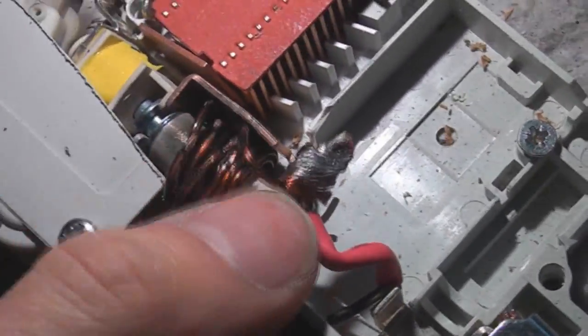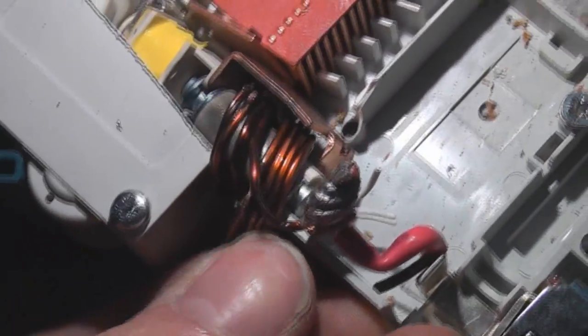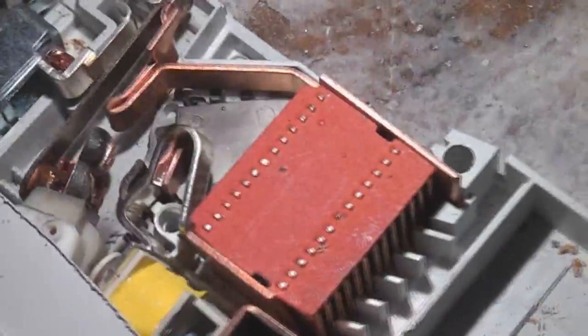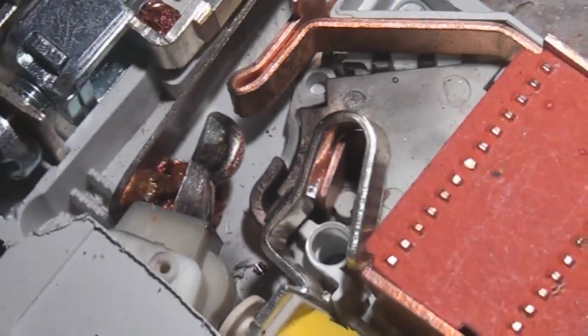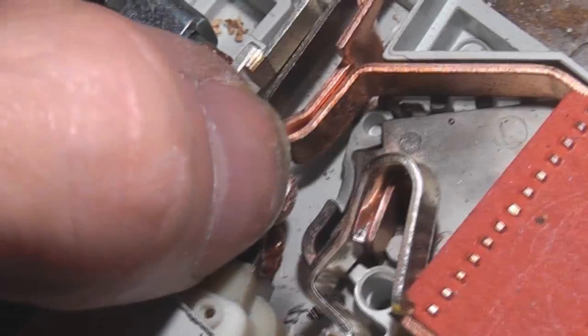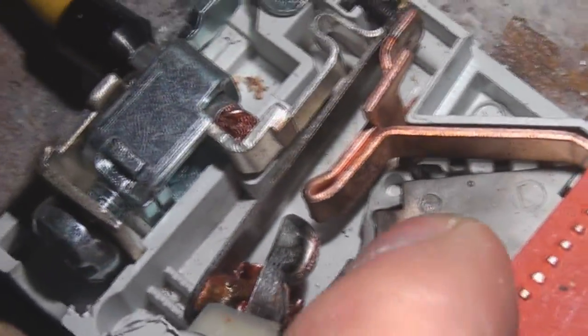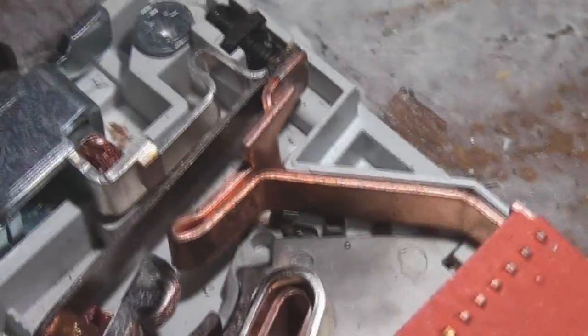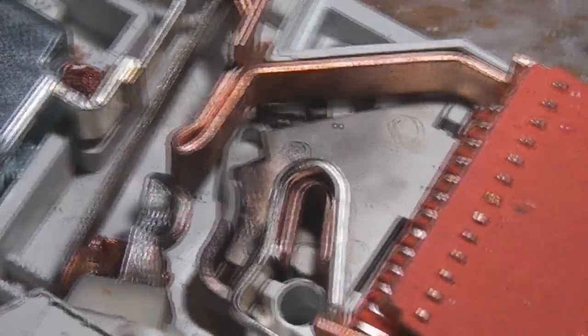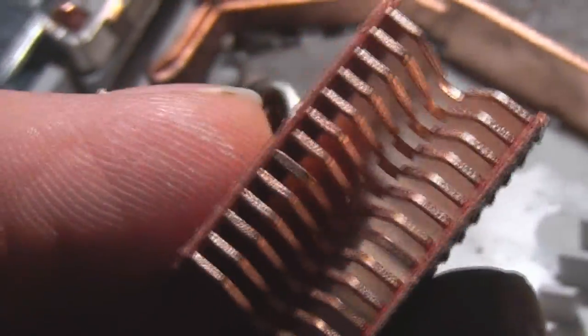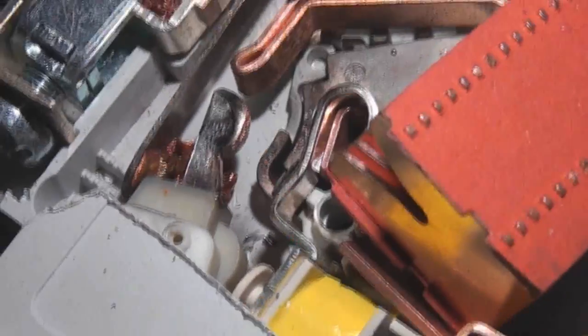Now, unfortunately, this has done a bit of fairly serious damage. It disintegrated the coil. We can see some of the flash. We've got some pitting of the contact, and we can see a bit of the arc flash, which deposited some metal on here. Can't actually see any evidence of it having travelled down or into here, though. I think it's just everything went off a bit too quickly.